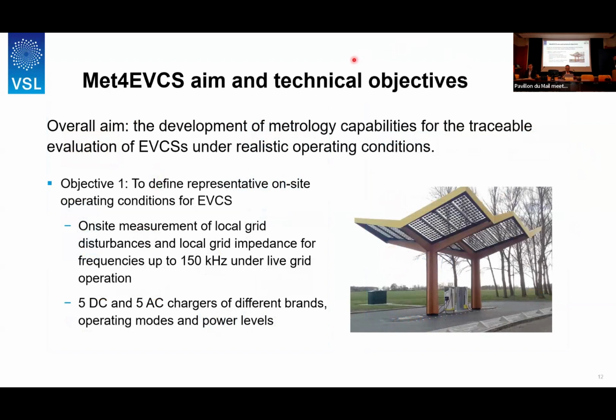So what is this project aiming for? The overall aim is the development of metrology capabilities for the traceable evaluation of EV charging systems under realistic operating conditions. I now realize I forgot to mention we have the abbreviation EVCS, which is charging stations, but you might have seen another abbreviation in previous sheets sometimes, because they also use the abbreviation EVSE, which stands for supply equipment, but it's one and the same thing, basically. Anyway, so the first objective of the project is to define representative on-site operating conditions for EV charging stations, and by that we mean up to 150 kilohertz and both the disturbances themselves and the grid impedance. And we promise to measure at least 5 DC and 5 AC chargers.